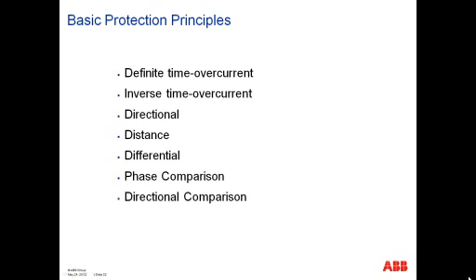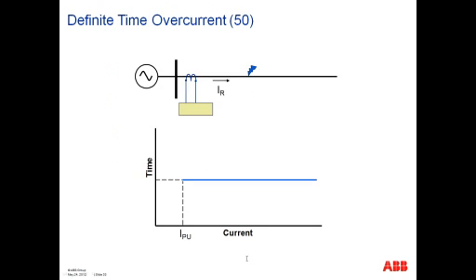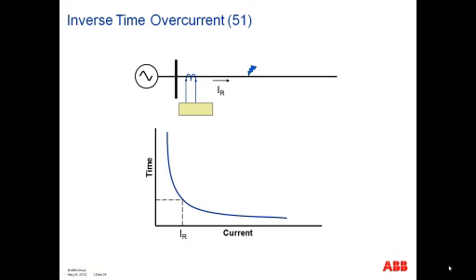Basic protection principles. We're going to address these characteristics, if you will, that I have shown on this page. Definite time, overcurrent, inverse time, direction, distance, differential, phase comparison, directional comparison. A definite time overcurrent, as it states, operates at a set time, and this time could be instantaneous or some set time. For any current at or above the pickup level, the relay would operate. So its characteristic is a straight line.